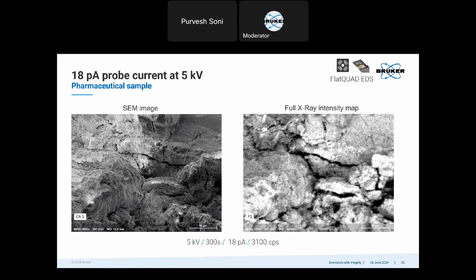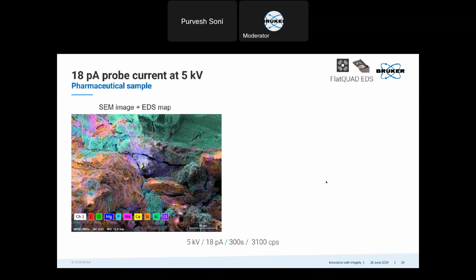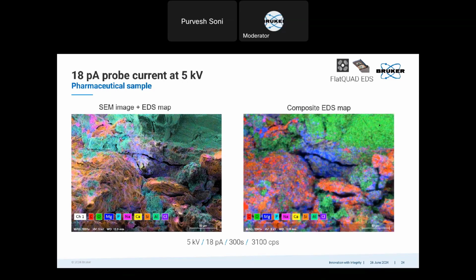And this is the full X-ray intensity map. So we can see that the sample is highly topographic, charging, and there are at a very low probe current, and we still have a very filled X-ray intensity map. And yeah, there is barely any shadowing. There is only data which is missing from the cracks. And this is the SE overlaid chemical map, and this is the composite EDS map. So yeah, you can see how nicely all the features are resolved, even at such low probe current for a heavily charging sample.